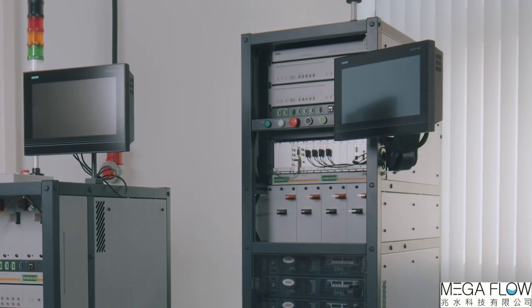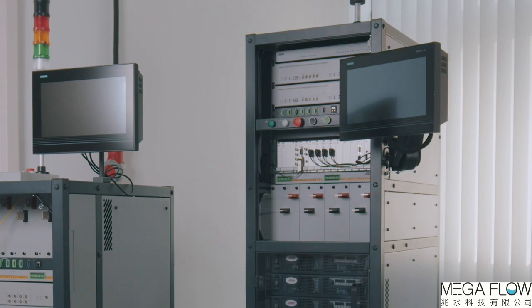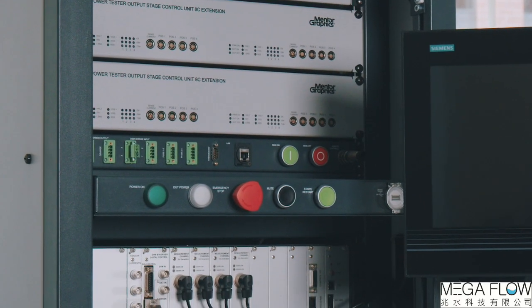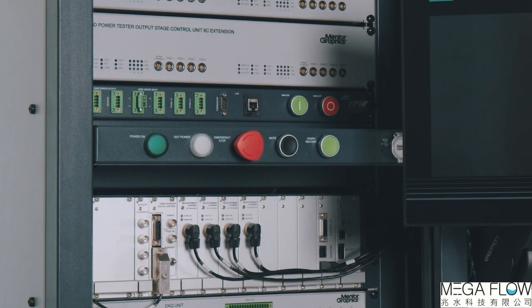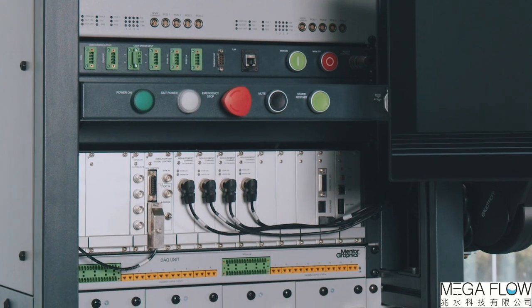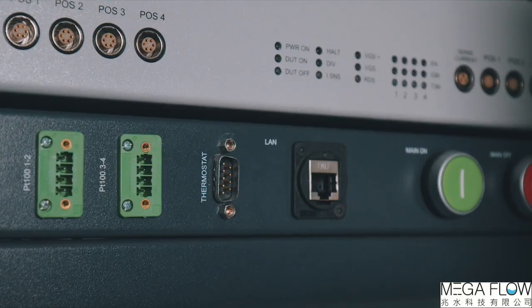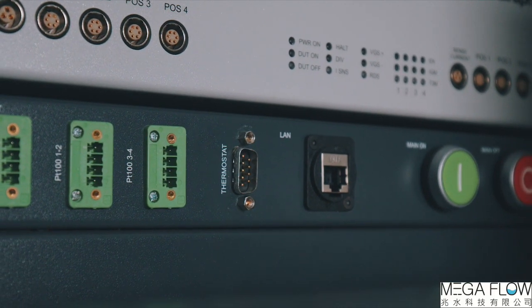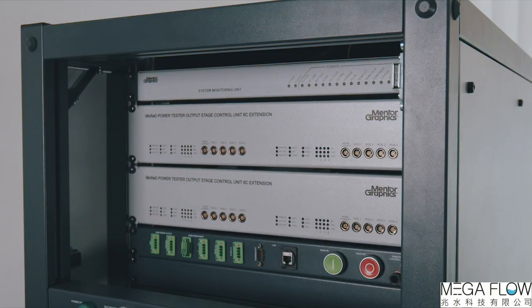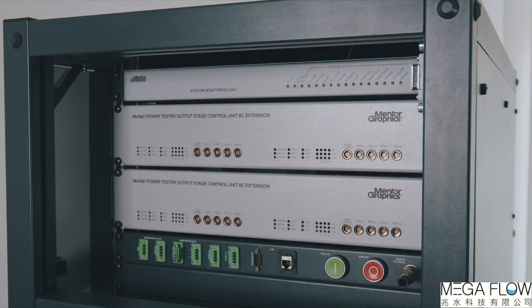This power tester contains no cold plates or closed measurement space. It is built into a 19-inch rack, which allows minimal system footprint and facilitates simple connection to external measurement environments.